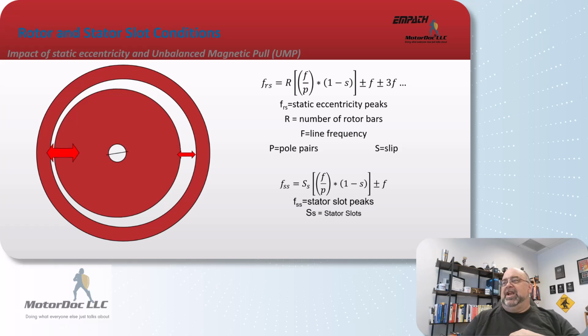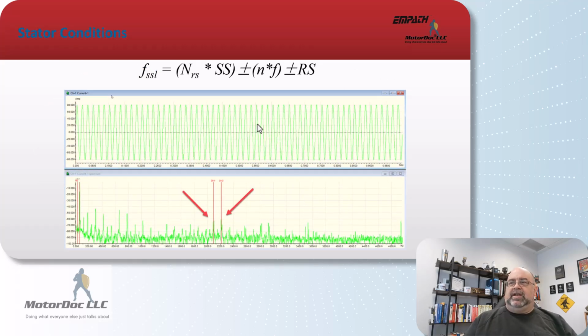So running speed peaks, rotor here, stator here. This is the actual formula for it. Why not? It all has to do with the unbalanced magnetic pull. And then, of course, the stator slot frequency here: if I have line frequency sidebands or a high raised noise floor around either one, that's indicating an insulation breakdown. That was our other paper. This is one of several. There are 4 types of insulation breakdown we identified and how they're derived.